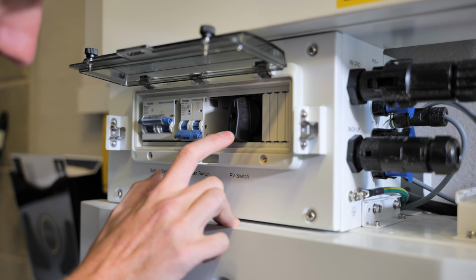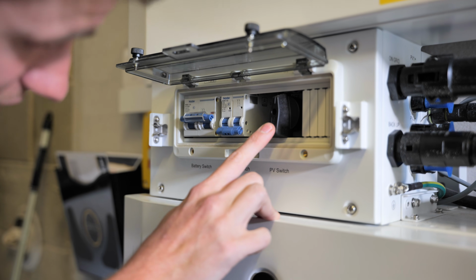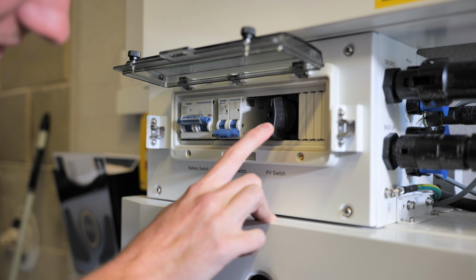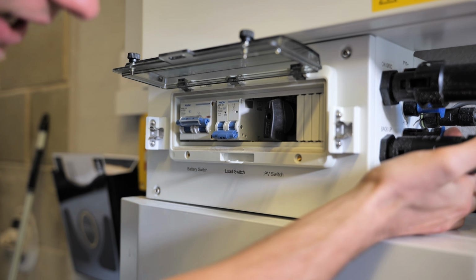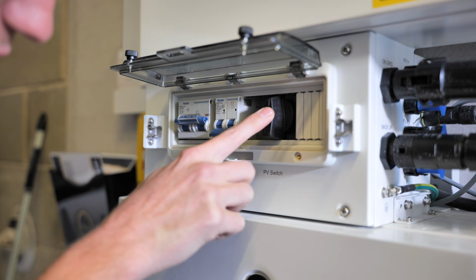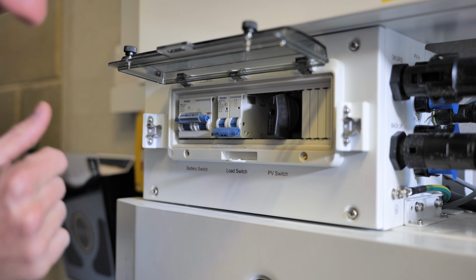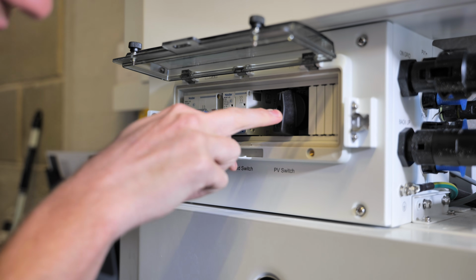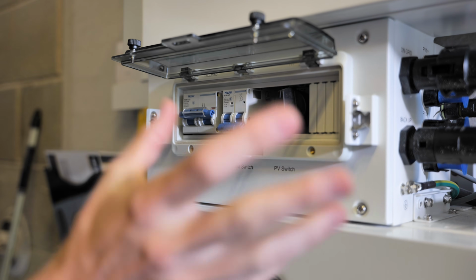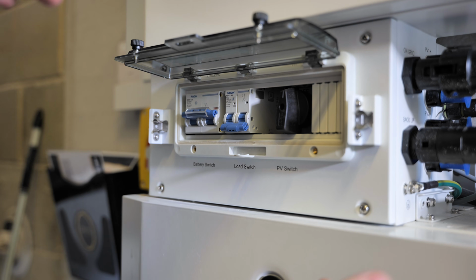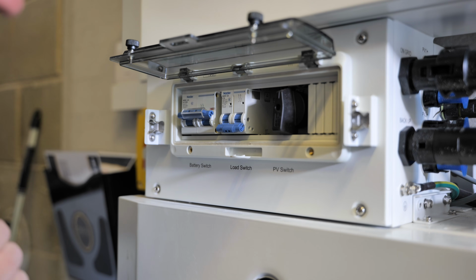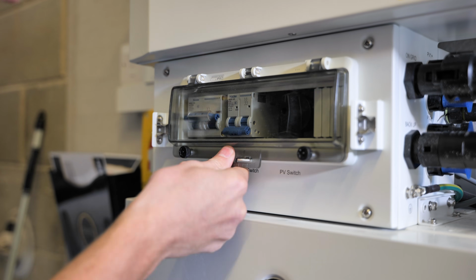We've then got a ProJoy DC isolator. Again, if we had solar PV feeding directly into this through those MC4 connections I mentioned, then this would be on, and that would allow the DC to enter the Libbi inverter - this is just a local means of isolation. We would also have another one or two of these on the outside of the inverter, depending on how the system was set up, but the inverter comes with one inside it as well. That's there.